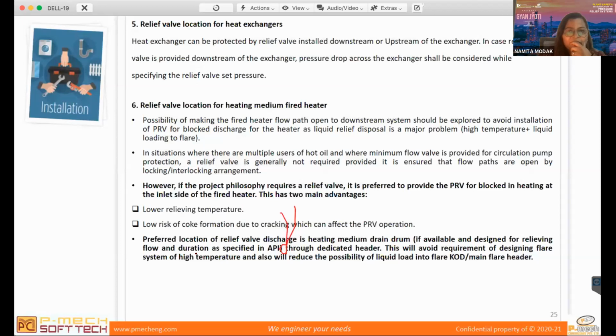On heat exchanger, you will see there are three scenarios where we give a PSV. Let's say this is the inlet, this is the hot side and this is the cold side system. If the cold side is blocked in and the hot side is still running, because of this heat transfer there's a temperature rise on the cold side. So you need to give a PSV. It is also called a thermal safety valve.